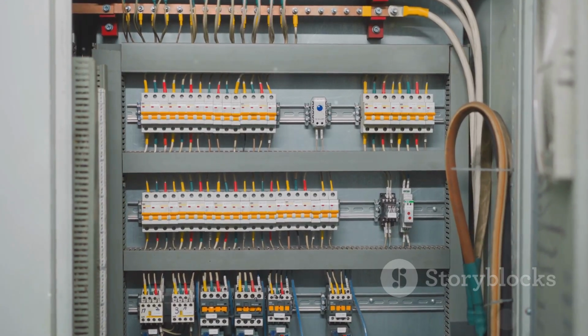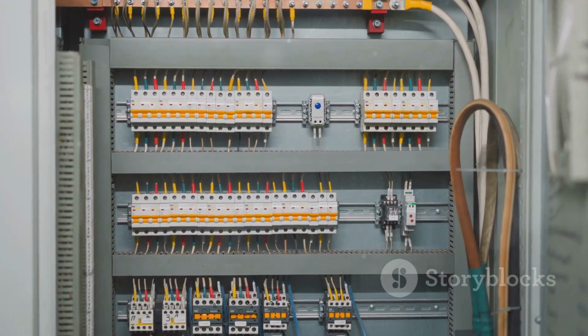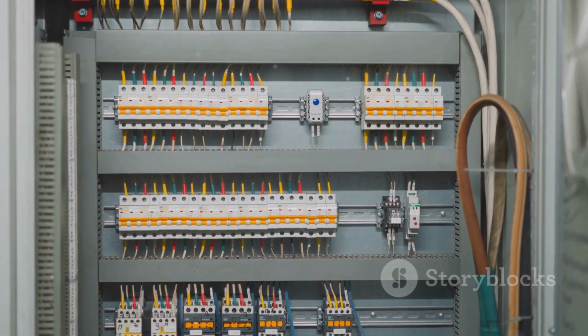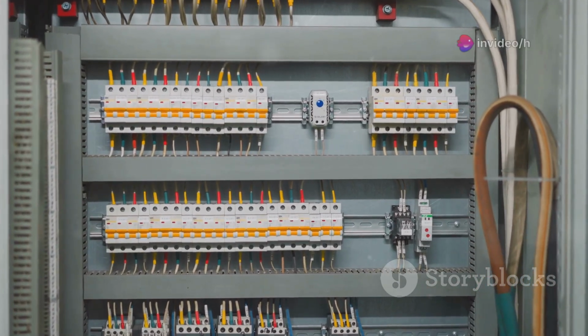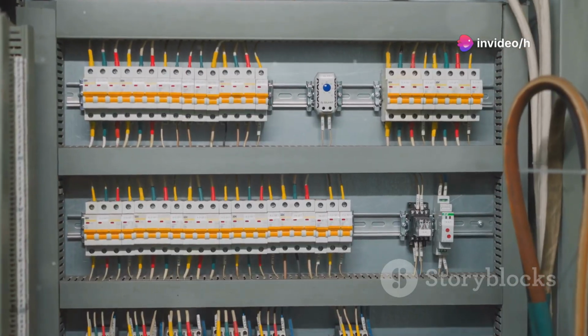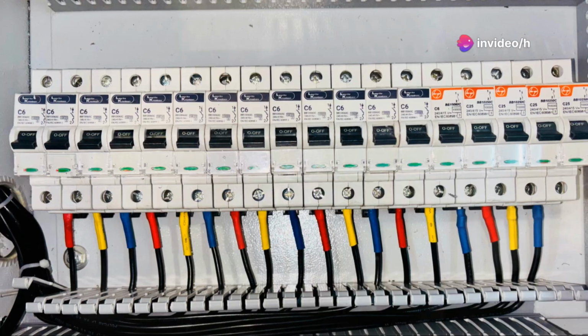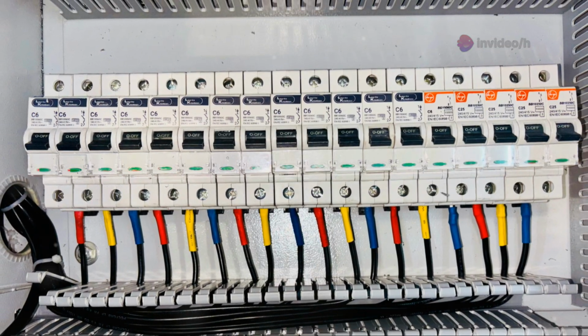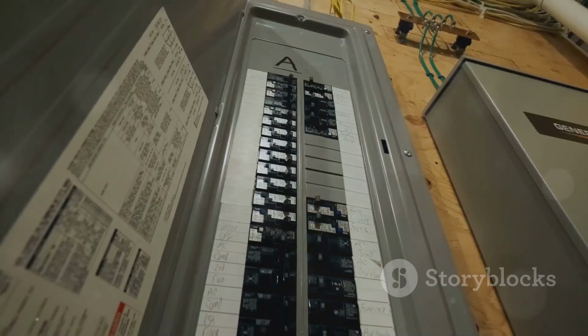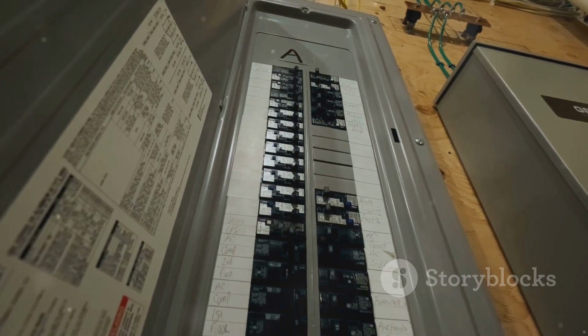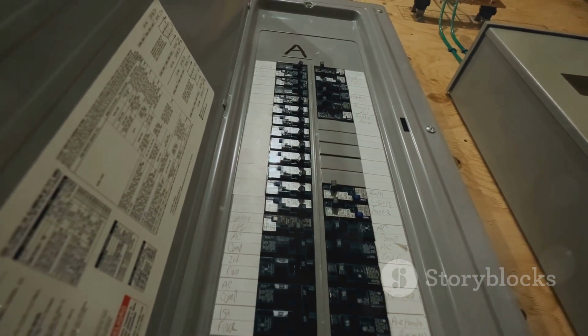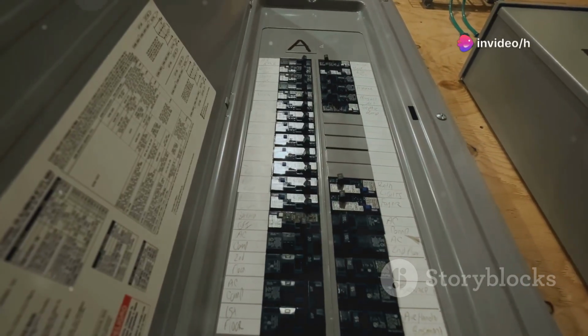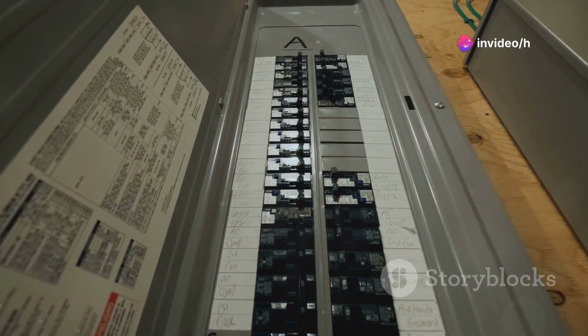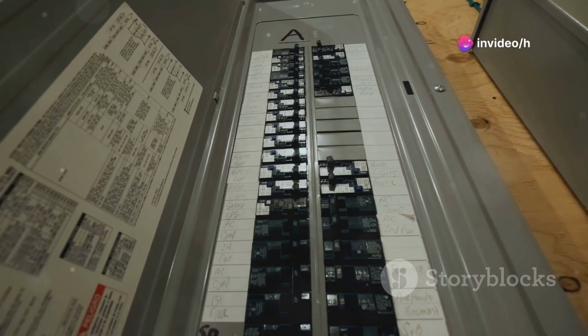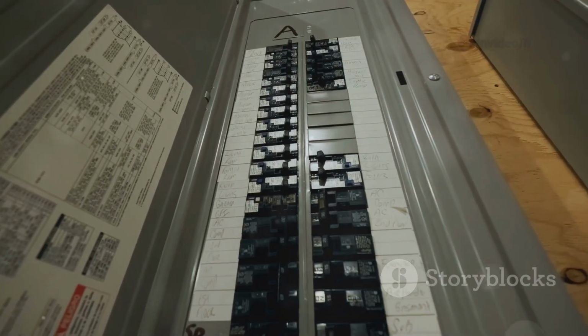Next, add the MCBs, miniature circuit breakers. Install one MCB for each single-phase motor and two 3-pole MCBs for the 3-phase motors. This setup ensures that every motor, regardless of its type, is individually protected from electrical faults. MCBs are designed to trip automatically during overloads or short circuits, preventing damage to your equipment and reducing the risk of fire. They act as guardians for your machinery, ensuring that any electrical fault is quickly isolated.